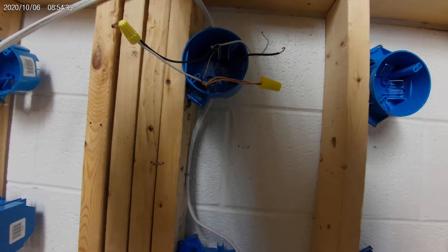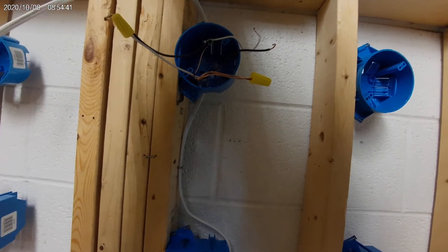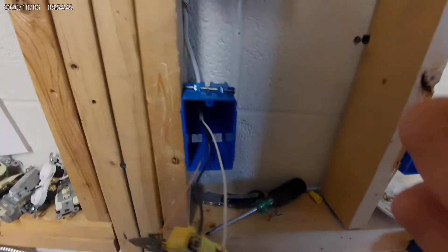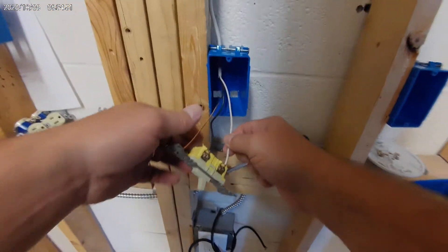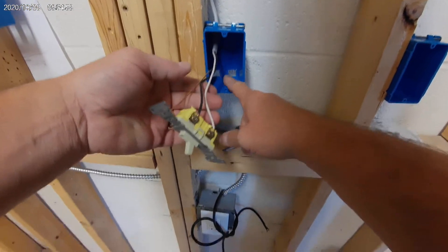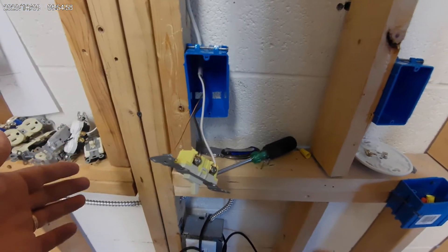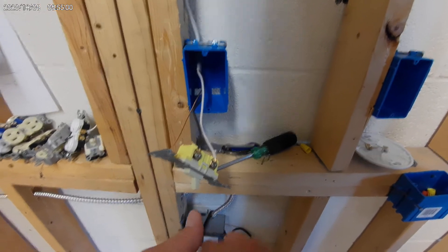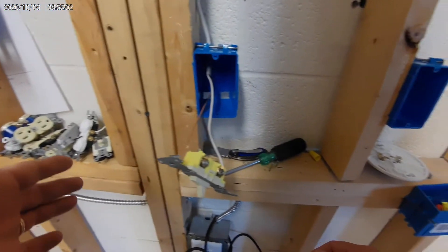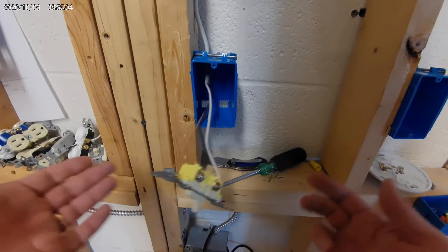This in residential wiring now is illegal. We can't use this because as you notice, when we get down to the switch, in the switch box I have a hot and a load. I no longer have a neutral. Some of our newer electronic switches require a neutral. Or if I want to tap an outlet off of this, I don't have a neutral anymore.